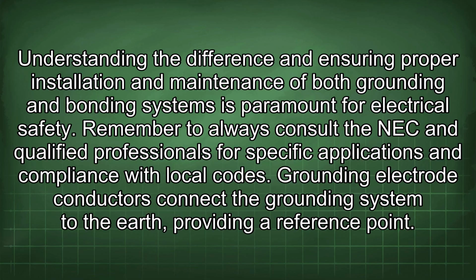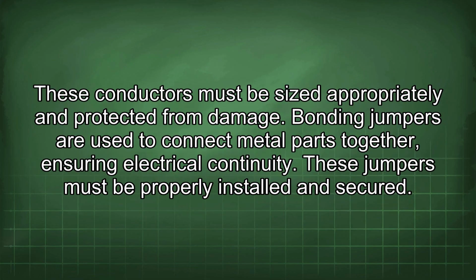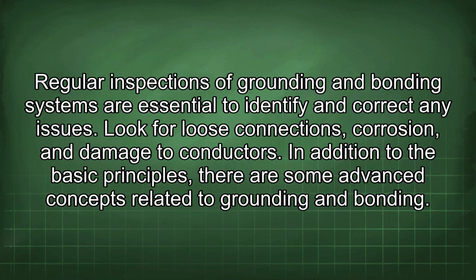Grounding electrode conductors connect the grounding system to the earth, providing a reference point. These conductors must be sized appropriately and protected from damage. Bonding jumpers are used to connect metal parts together, ensuring electrical continuity. These jumpers must be properly installed and secured. Regular inspections of grounding and bonding systems are essential to identify and correct any issues. Look for loose connections, corrosion, and damage to conductors.